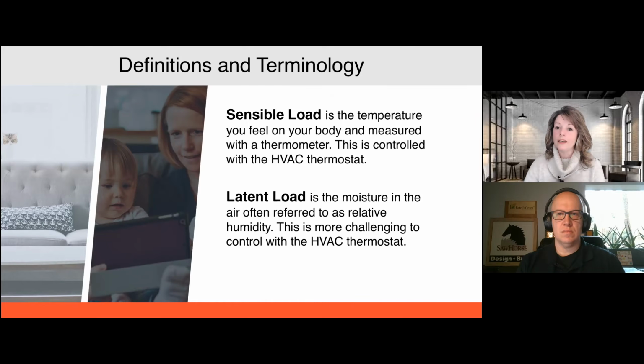And so there are a lot of calculations like Manual J that are very important when it comes to sizing our air conditioners, because we want to make sure that we're getting to that sensible temperature, but also maximizing the water removal in getting there. So it's important to know what our Manual Js are and that our air conditioning equipment is sized correctly for the homes or buildings that we're applying it to, in order to make sure that we are getting the maximum amount of water removal possible when the air conditioner is running.